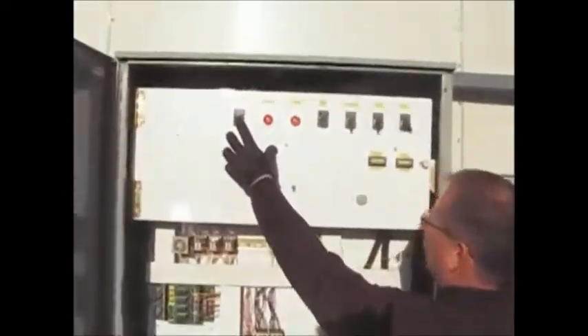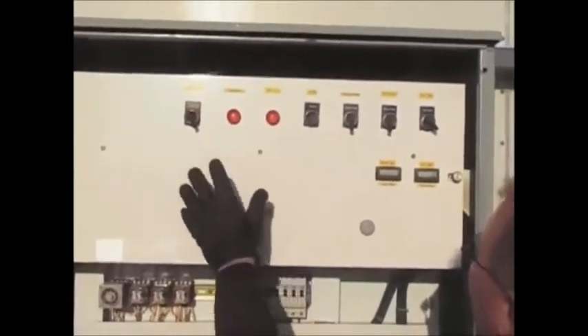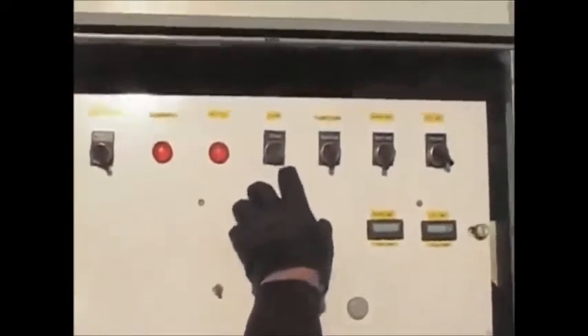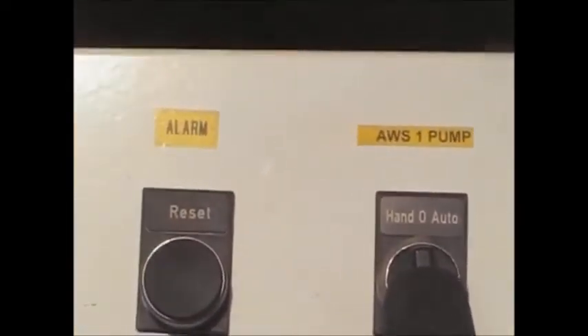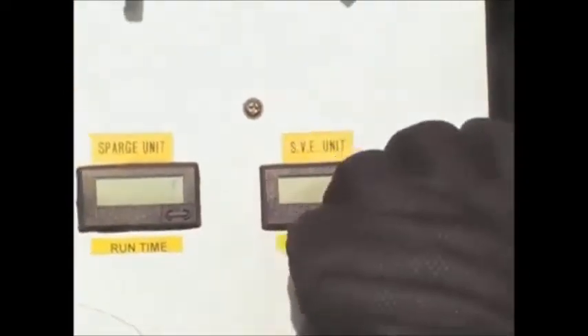This system has very basic controls. Currently has no telemetry at all. It's strictly relay based, so everything has a hand-off-auto switch. There's an e-stop inside the trailer that, if you're in there working and you need to shut the system down, you can shut it down. Out here though, to reset any alarms, you have a reset button. Again, you have hand-off-auto switches for your air-water separator transfer pump, Sparge unit, and then your SVE hour meters for the Sparge unit and the SVE.